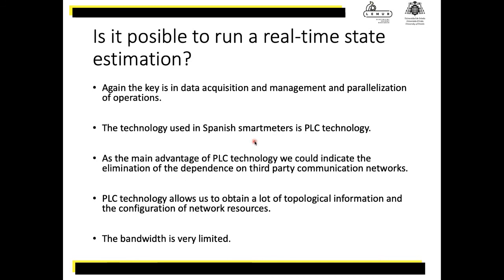In Spain, let me talk a little bit about the system that we have for getting the data from the smart meters. We are using PLC technology, power line communication technology. This is a technology in which the smart meters inject the data into the electric wire. Then I filter this high frequency signal at power transformer level, so I get the data from the smart meter.